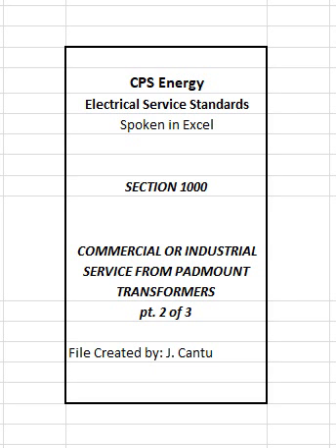C. Inspections. Two inspections are required for transformer slabs. A CPS Energy inspector shall inspect the slab after forms, reinforcing steel, primary and secondary conduits, metering conduit, and ground rods are in place, and the installation is ready for concrete pouring. A second inspection is required after the concrete has been poured and all forms have been removed. COSA or other AHJ inspectors do not make these inspections.